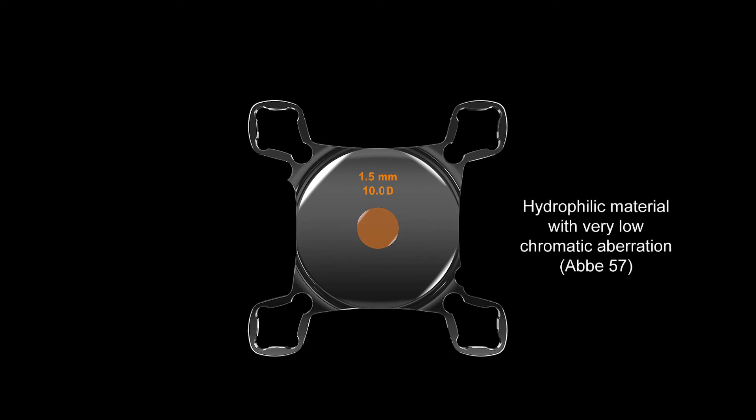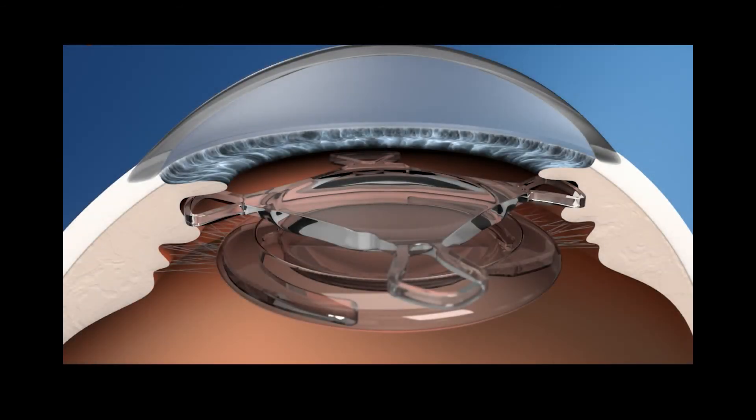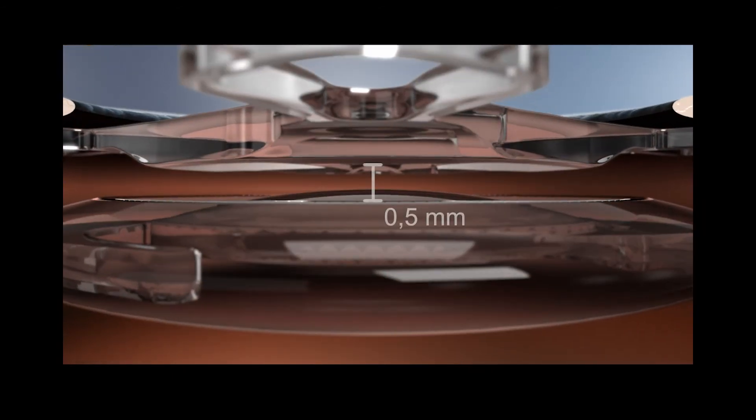The macular lens has a central portion of a specially designed optic of 1.5 mm and an addition of plus 10 diopters. The IOL is made of hydrophilic acrylic material. The edges are round polished, preventing iris chafing. It has a square design to prevent iris capture, and the optic is a convex-concave design that ensures a space between the intracapsular lens and the add-on lens, preventing interlenticular opacification. The central optic of plus 10 diopters does not disturb far vision.